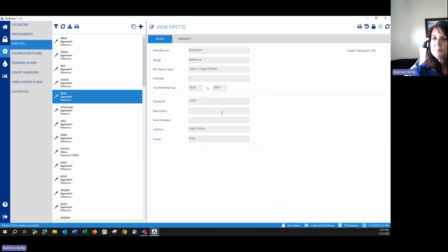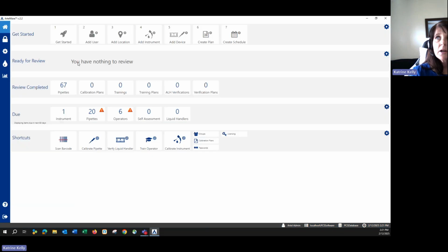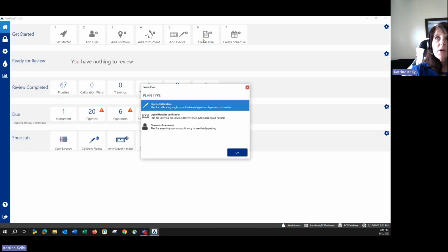And click OK. So now I have all of my pipettes entered into the software. The next thing I need to do is set up a pipette calibration plan. Now, if you're setting up liquid handlers, you would set up a liquid handler verification plan for the MVS. If you're setting up operator assessments, you need to tell the software what your operator assessment is going to look like. So the plan is number of data points and tolerance limits.